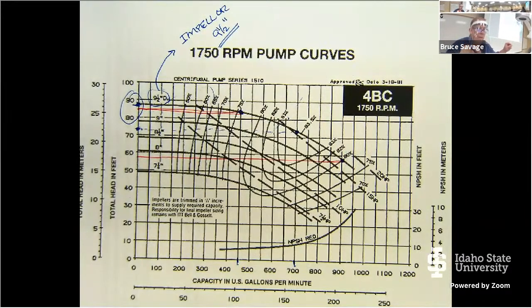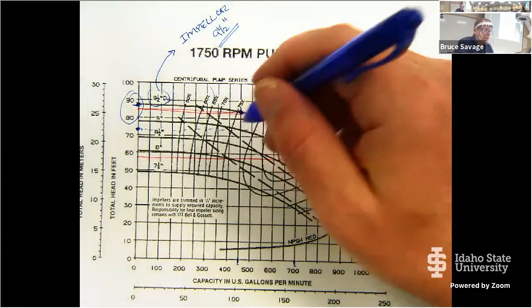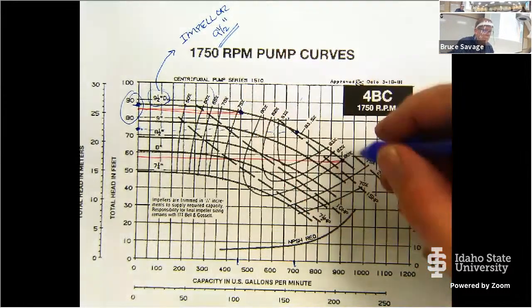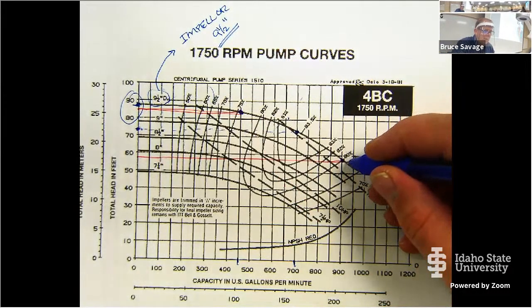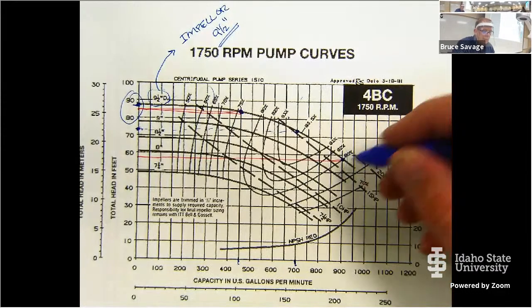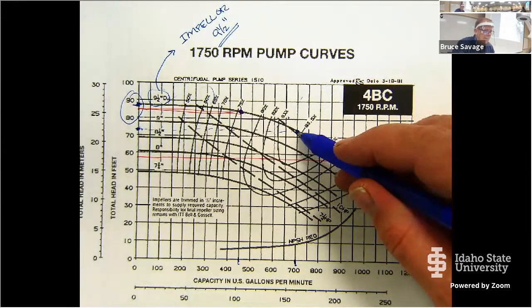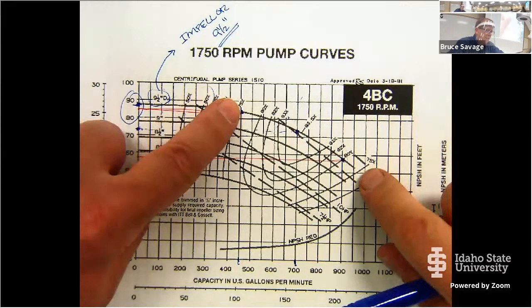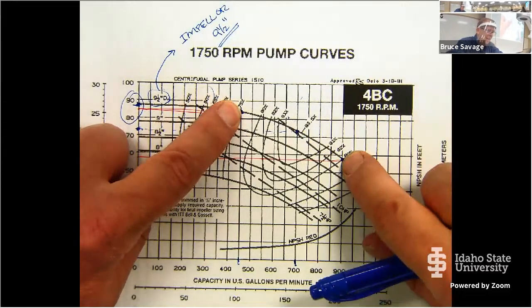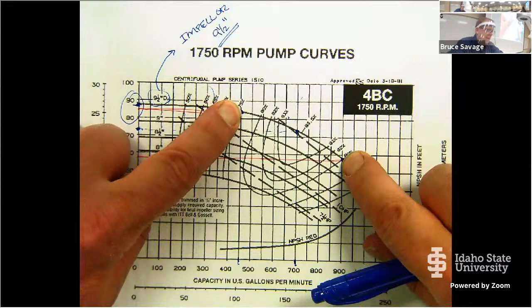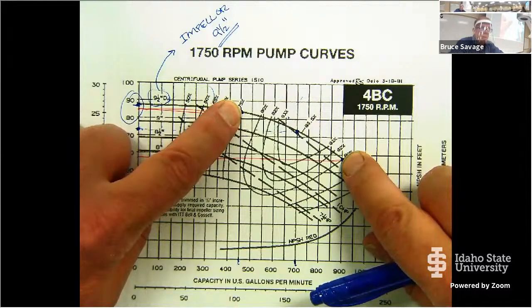Now, you may not always know that, all right? And so you might want to grab one here at 450 because that's halfway, and then come down here. Well, I did pick all the way to 900. Sorry, I said 700 here, didn't I? I bracketed it between 450 and 900, which is the majority of the range where the pump's going to operate. If I'm not operating my pump in this range most of the time, then I, or someone, selected a very poor pump for the system.